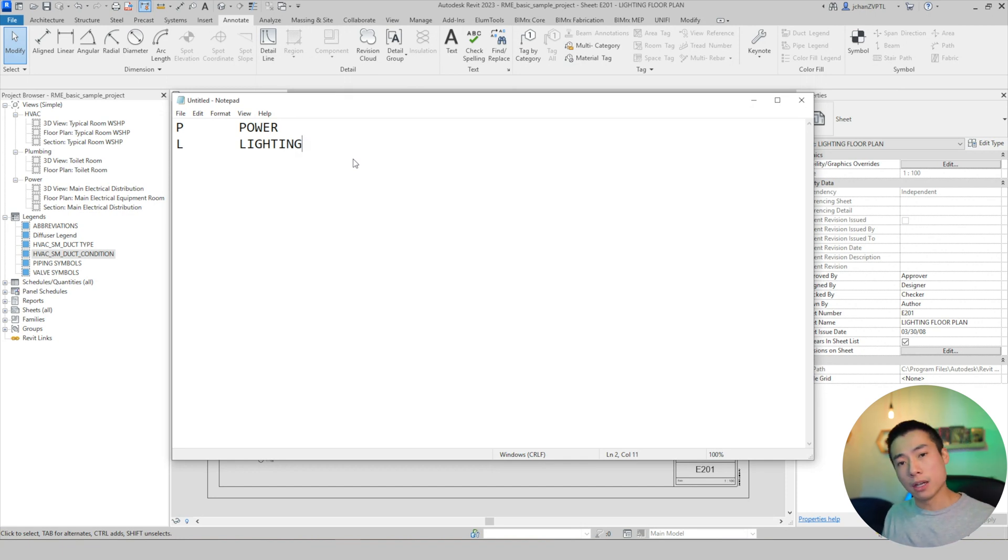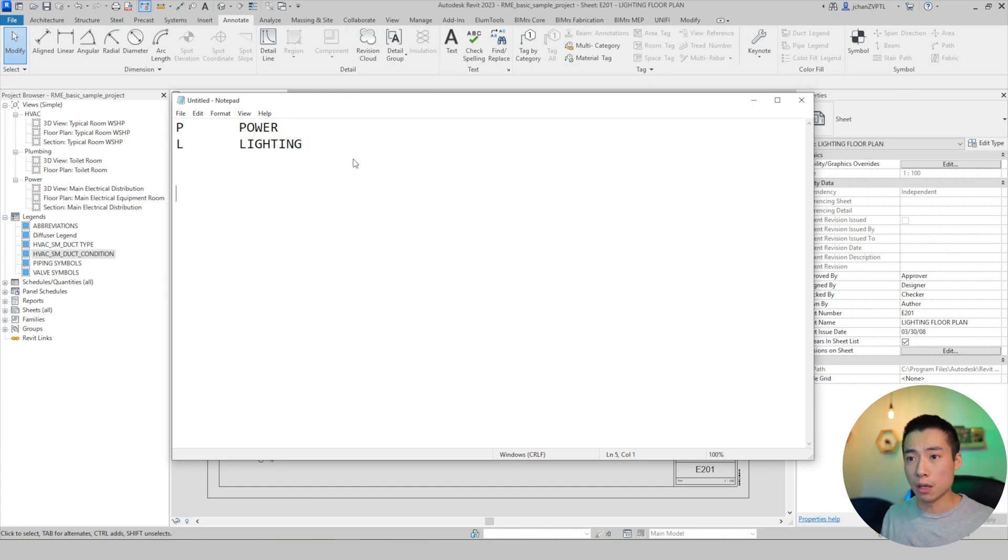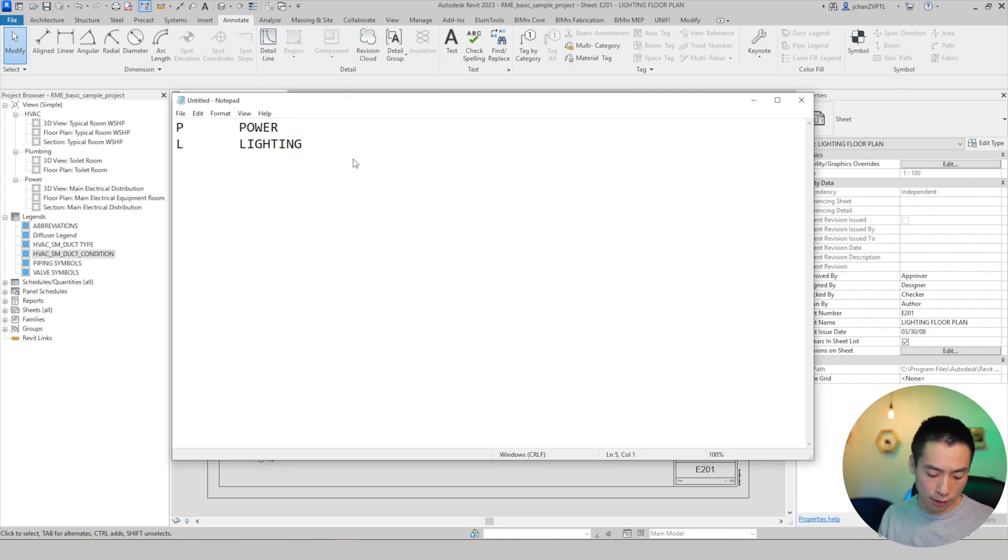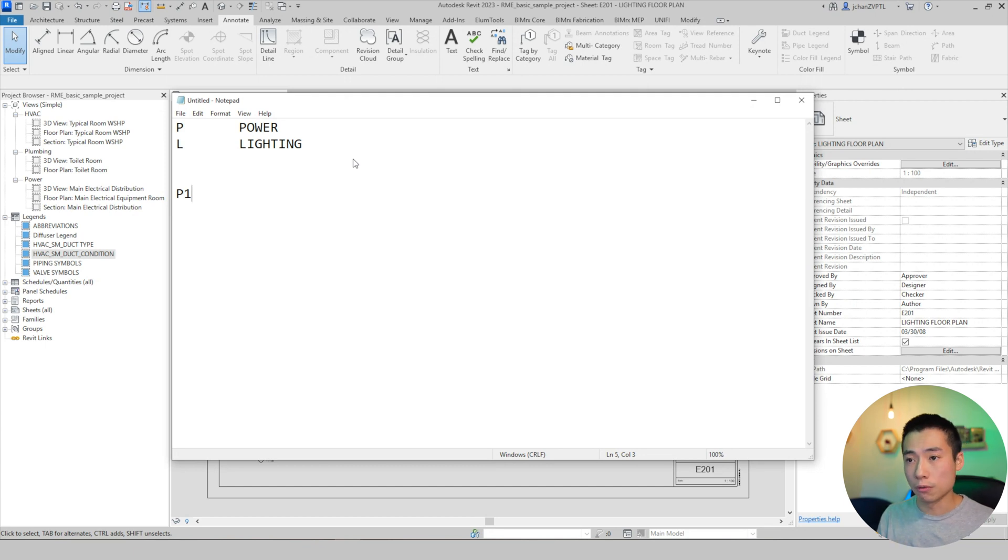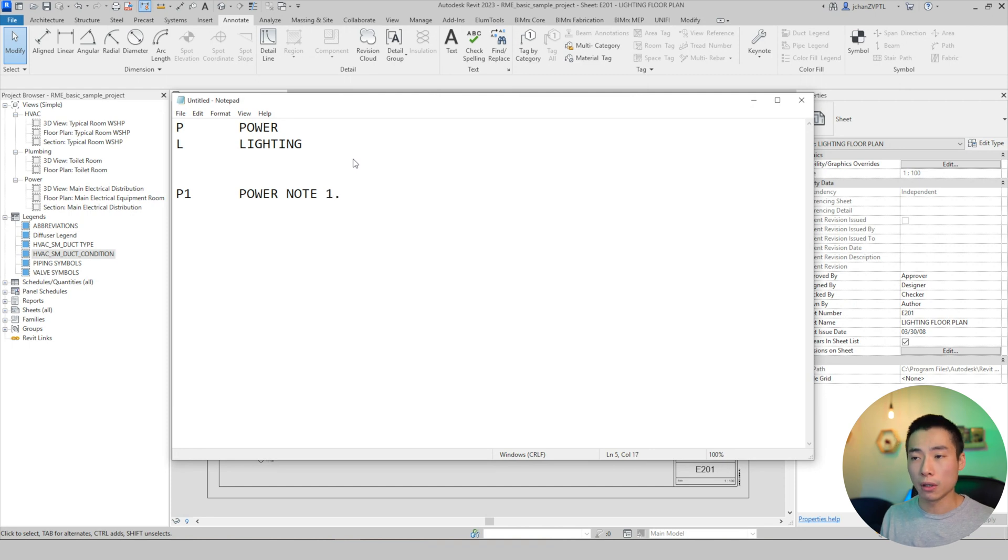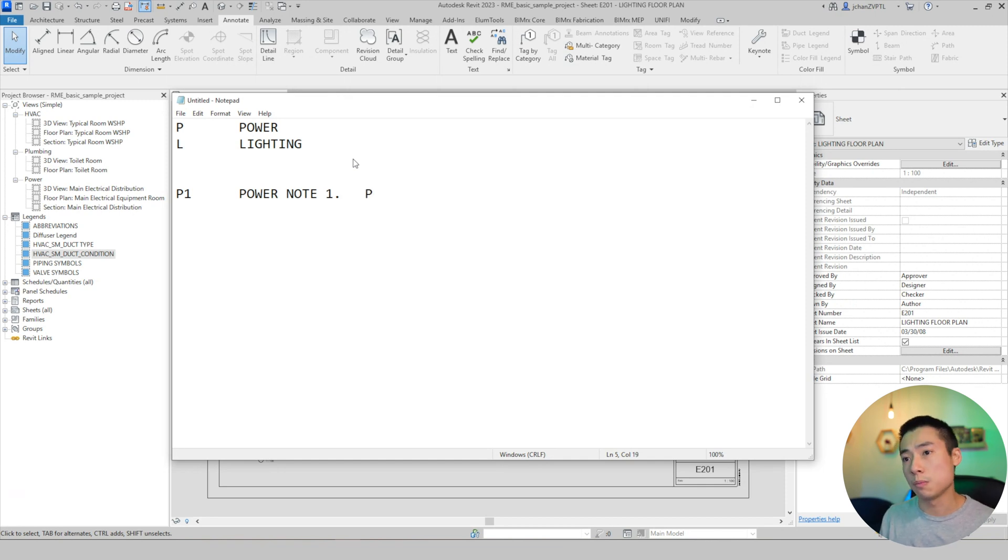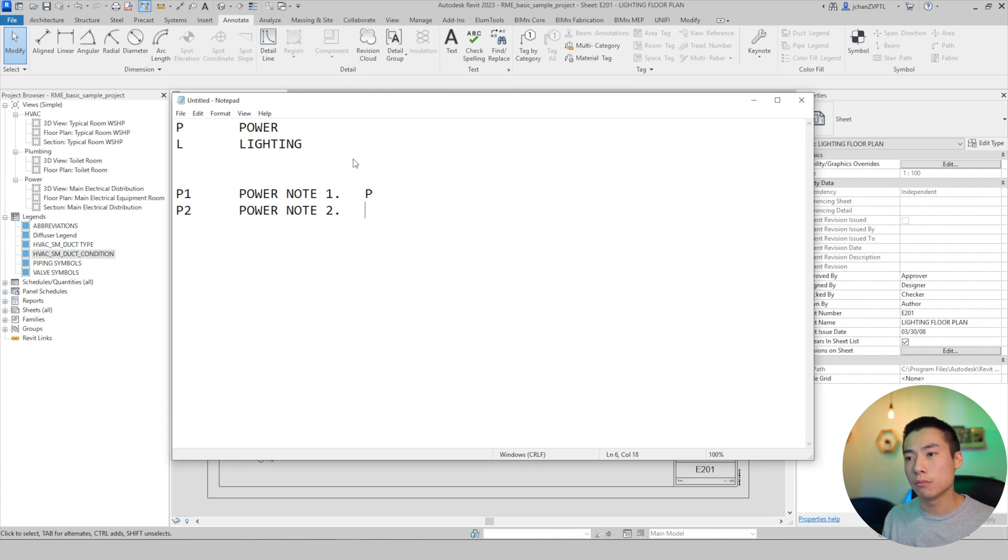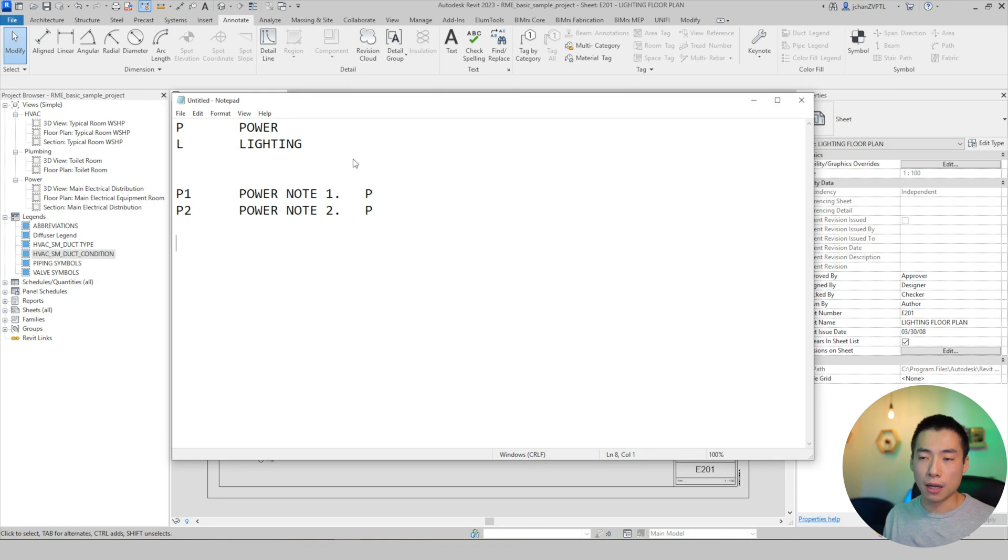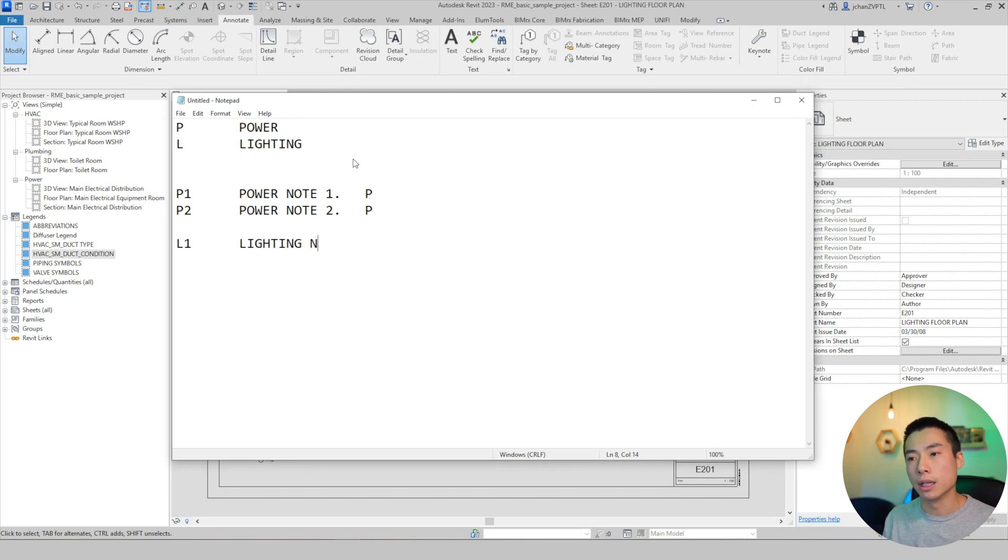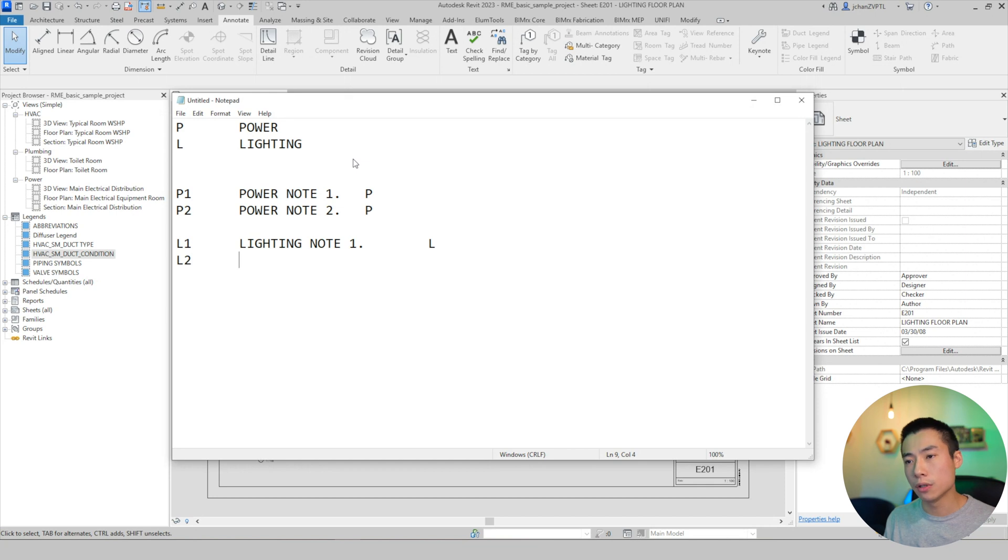So now that we defined our headers, we're going to put a few notes in so that we can link them in our drawings. So I'm going to press enter a couple of times to give me some space. And then I'm going to start off with let's say P1 for my first note. Then I can hit tab and I can do power note one period. And then you have to make sure that you hit tab and close it off with the same letter that you started with. So in this case, it's P so P2 tab, power note two, tab P. And then once you're done with one section, just hit enter a couple of times and you can start off with the next header.